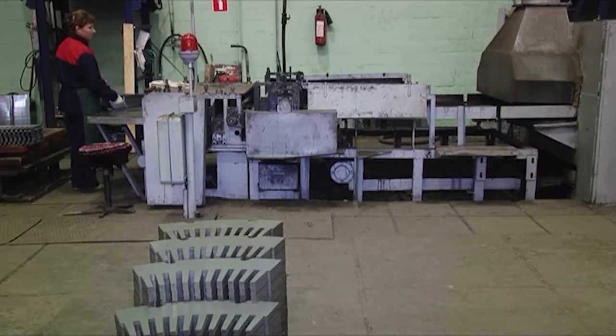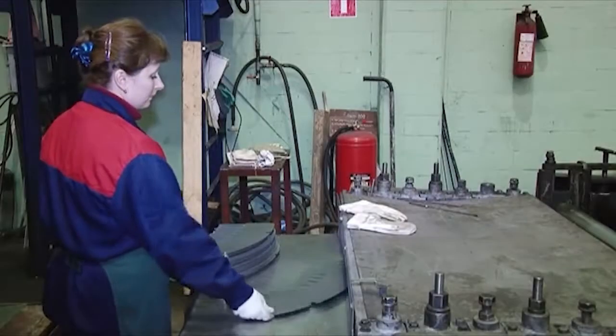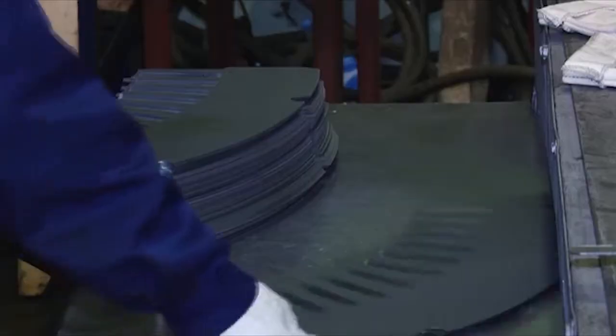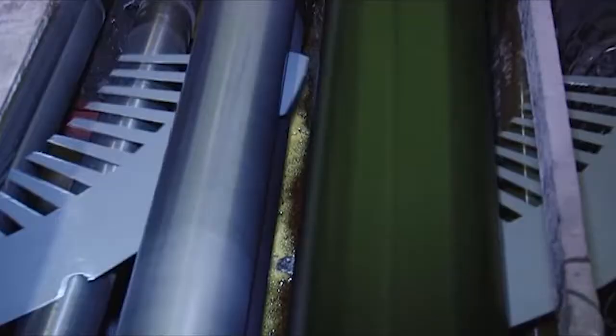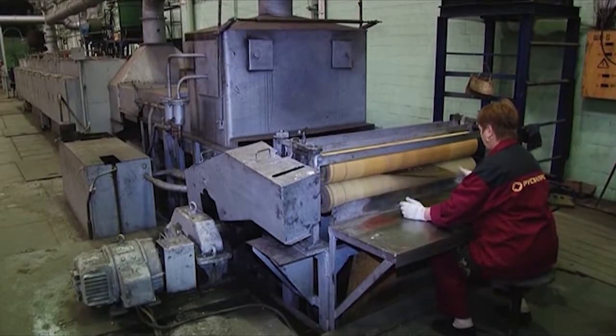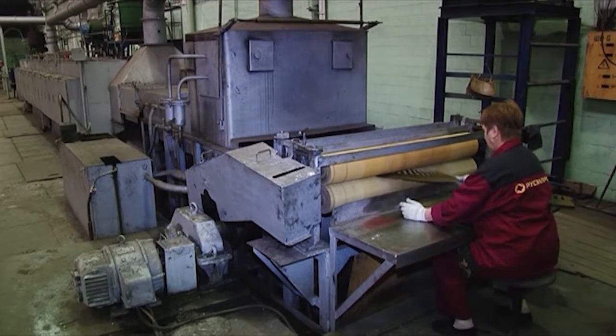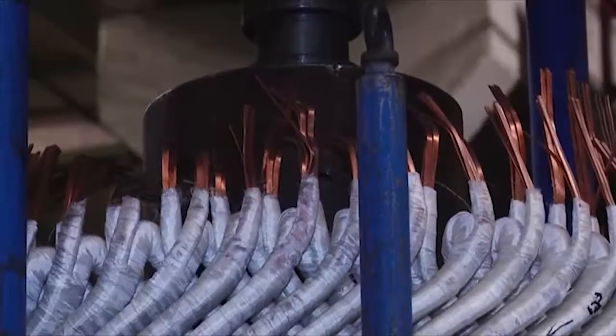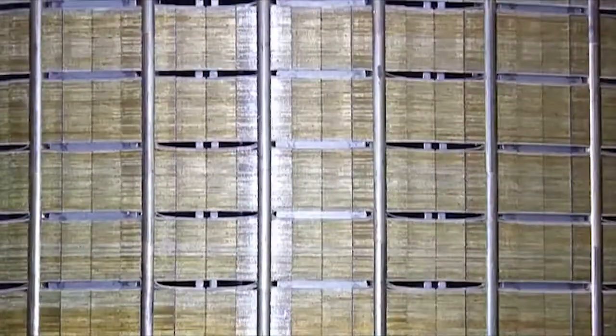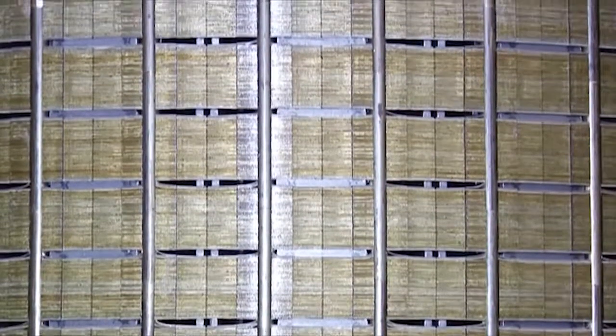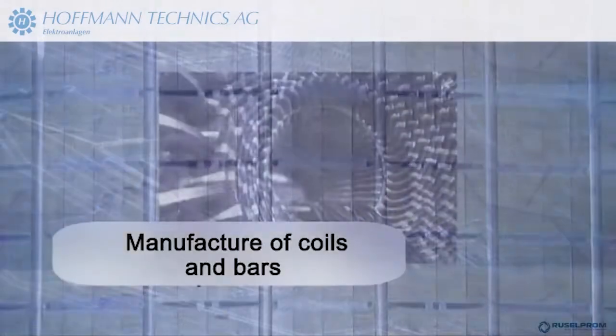The totally smooth surface of the segments is coated with special varnish to reduce power losses caused by magnetic circuit eddy currents. Then the segments are placed into a varnishing machine where they go through three main stages: coating with varnish, drying and cooling. The magnetic circuit may then be assembled and pressed together. Copper winding is installed into the slots after the completed manufacture of the magnetic circuit. These are either bar or coil windings depending on the motor type.